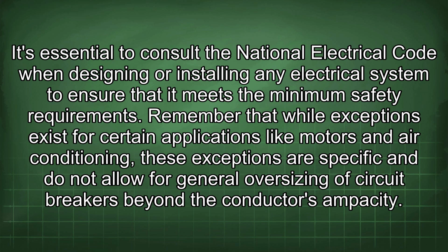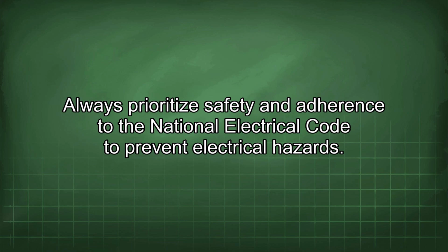Remember that while exceptions exist for certain applications like motors and air conditioning, these exceptions are specific and do not allow for general oversizing of circuit breakers beyond the conductor's ampacity. Always prioritize safety and adherence to the National Electrical Code to prevent electrical hazards.